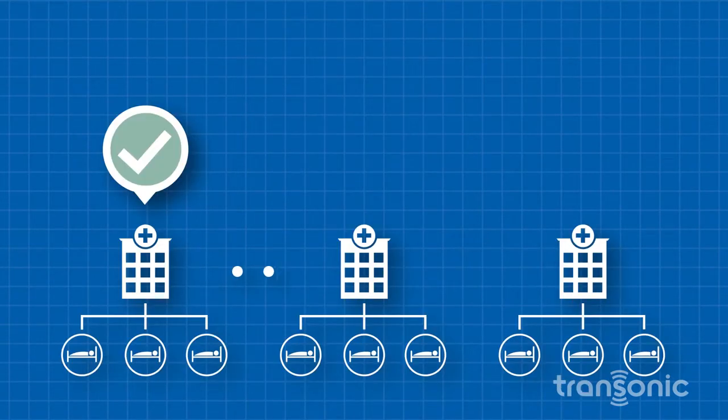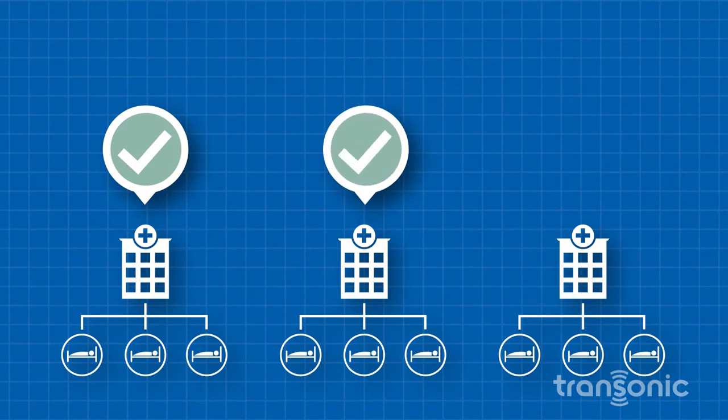The technician can move on to Clinic B, take measurements, and then synchronize the DTM to Clinic B's HD03 administrator software. This will transfer Clinic B's patient information to the DTM as well as reload the tubing list. Once finished with measurements at Clinic B, follow the same steps and then move on to the next clinic.